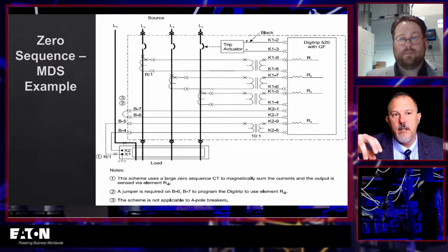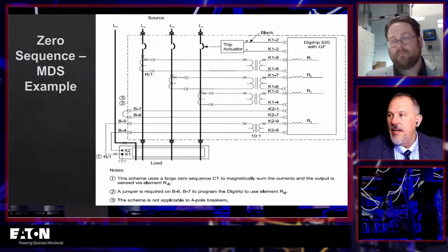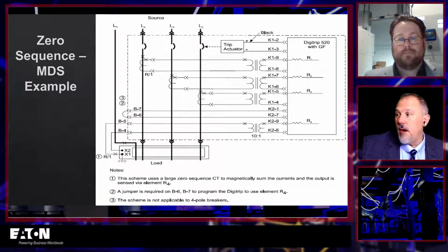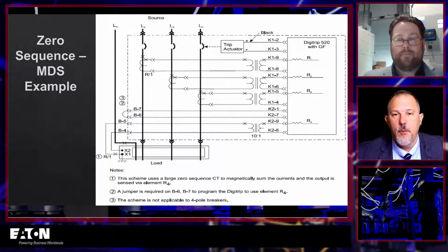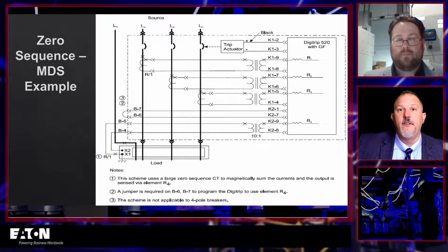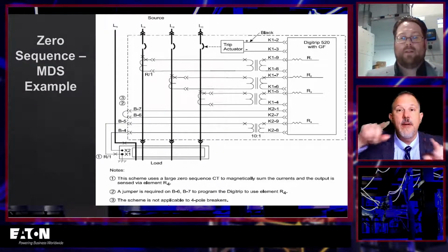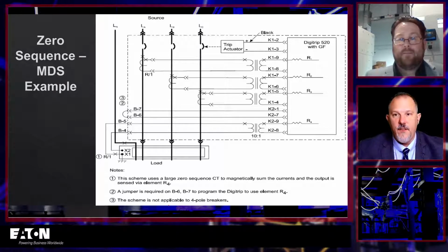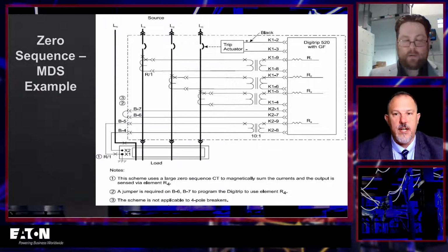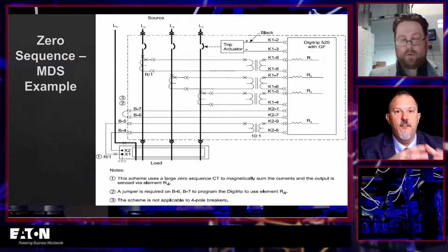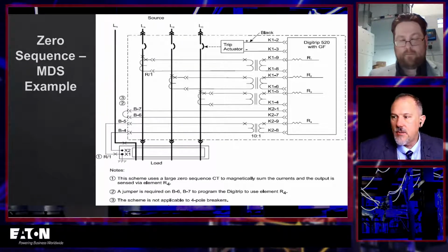I've done those calculations for some relaying, but mostly for metering, and there are other things in there. But on some of these, this is probably the only load, right? So you're more than likely not having to worry about a lot of different things hung off of this zero sequence CT. If it was a phase CT, you might have various relays doing 50, 51, 49, all those different types of relays giving you different functions that you have to think about. This one here is going straight into the breaker, so I don't necessarily have to worry about that.